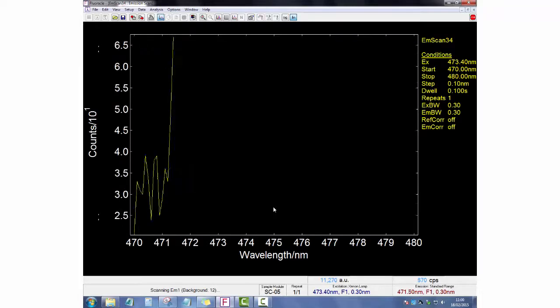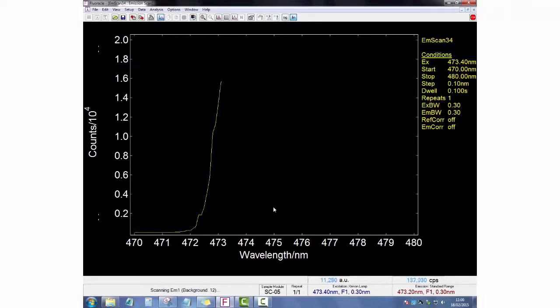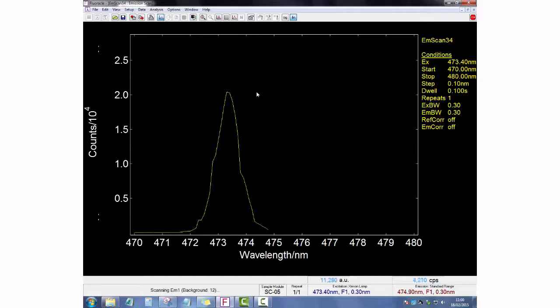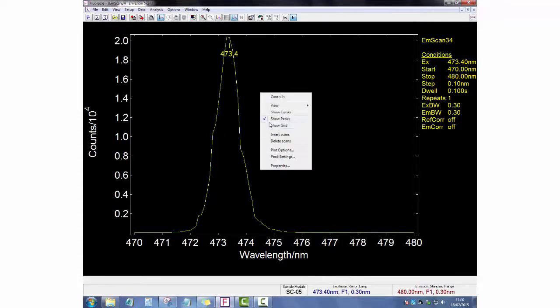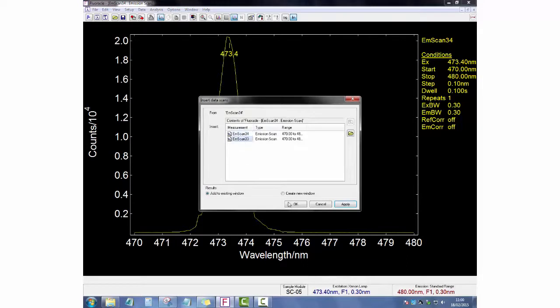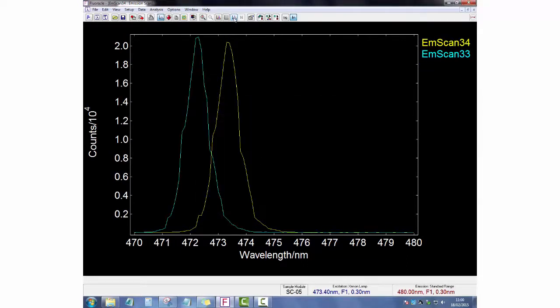Again, the software will adjust the emission monochromator calibration settings to ensure that the peak position is now at 473.4 nanometers. The calibration of both monochromators is now complete.